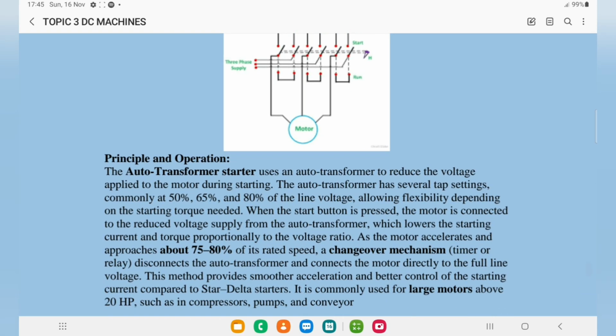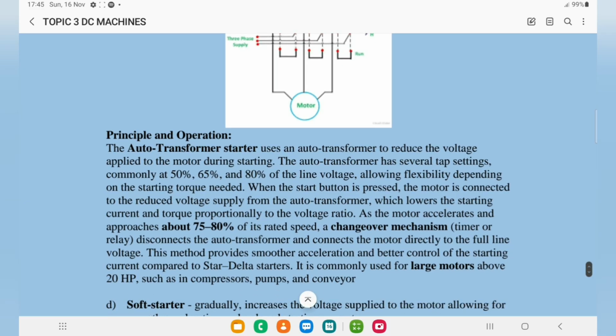When you're talking about its principle of operation, we say that this method uses an autotransformer to reduce the voltage applied to the motor during starting. Remember that an autotransformer has several tap settings, and the common ones are 50, 65, and 80% of the line voltage. This allows flexibility depending on the starting torque you need to drive a particular load. When you press the start button, the motor is connected to the reduced voltage supply from the autotransformer, which lowers the starting current and torque proportionally to the voltage ratio.